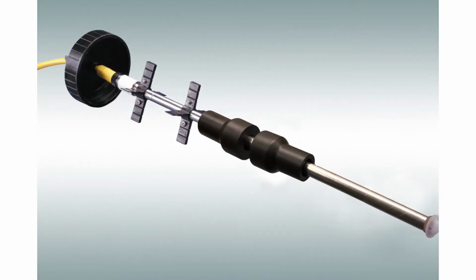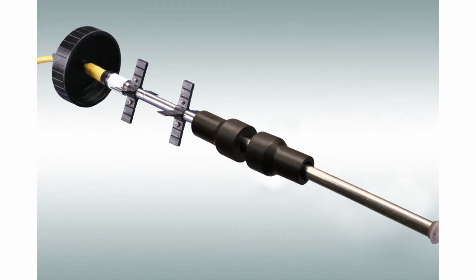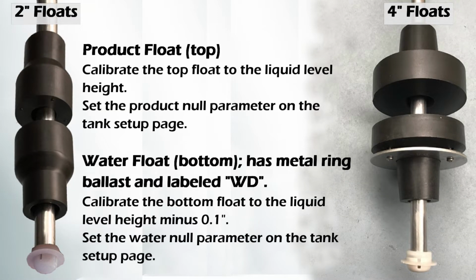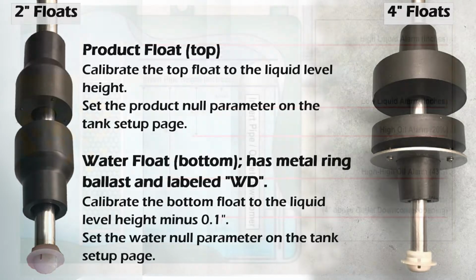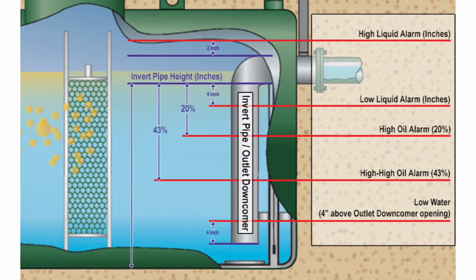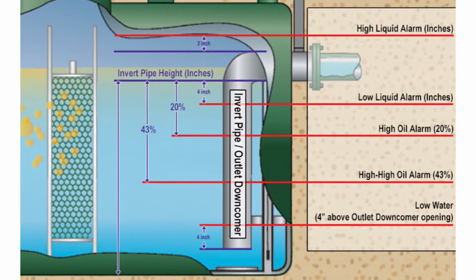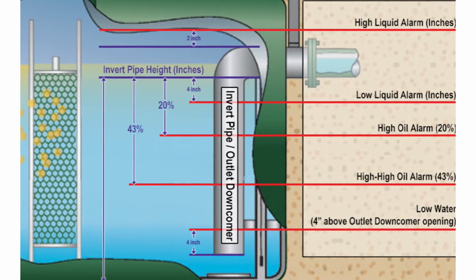The main difference is the floats are mounted in opposing directions. This configuration measures the height of oil floating on top of water. The measurement can be as little as 0.1 inch. Information is gathered from the oil water separator tank for the correct programming of the controller.